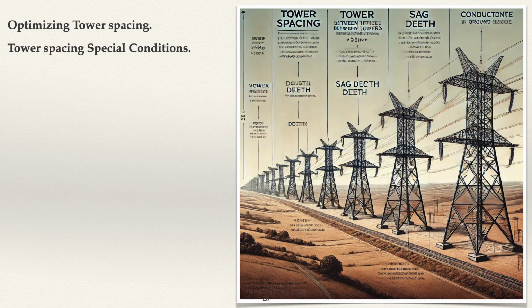To optimize the tower spacing, the following points can be considered. 1. Balancing cost and safety. Longer spans reduce the number of towers needed, but may increase conductor sag, requiring taller towers, and shorter spans increase tower density, leading to higher material and installation costs, but offer greater structural stability.